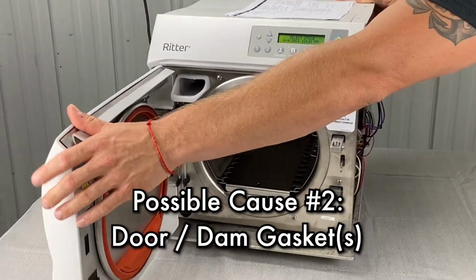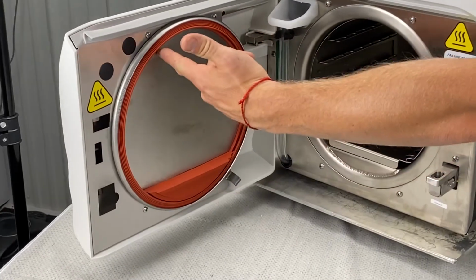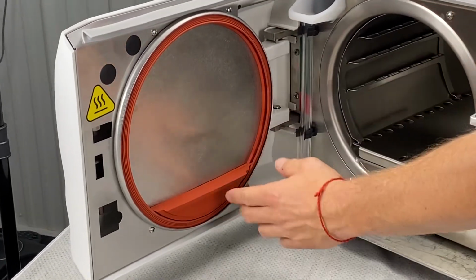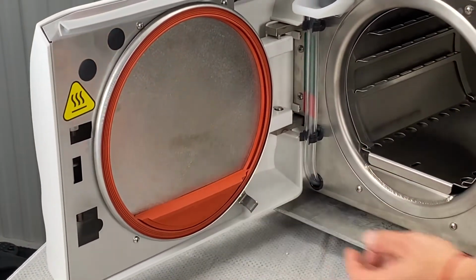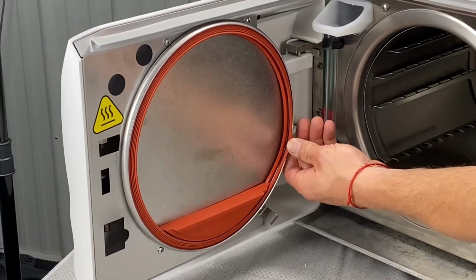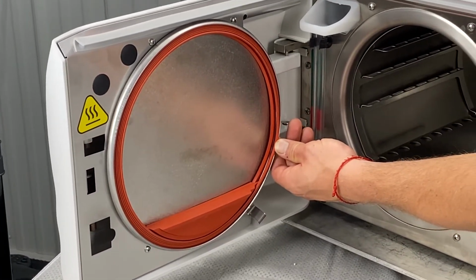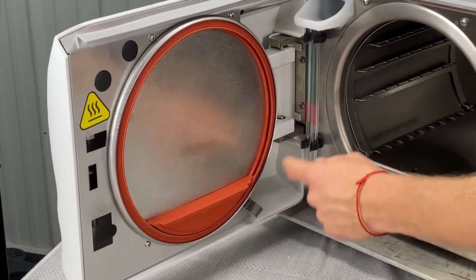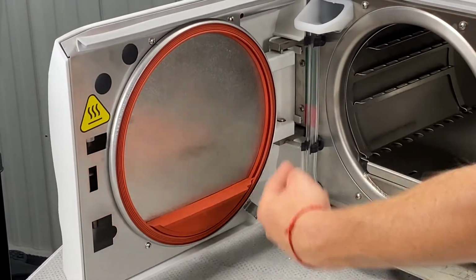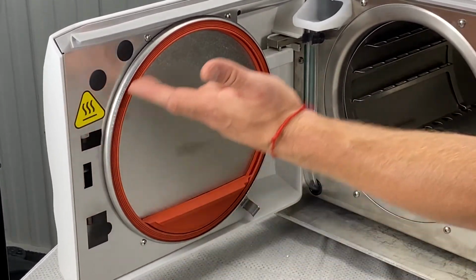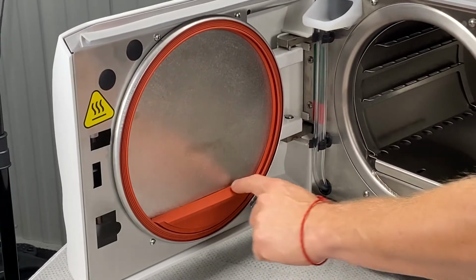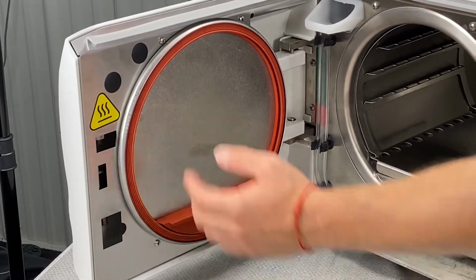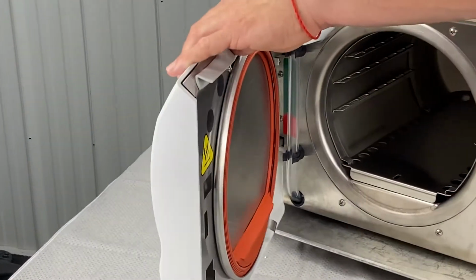Door dam gaskets, we're going to inspect those. They should be replaced quarterly, if not sooner, depending on cycle count and usage. But there should be a door ring in there. If you don't have one, you should get one. It makes the gasket last longer. But anyways, we're going to make sure that this is positioned properly, not sticking out anywhere. The dam gasket sits inside of the door gasket itself. We're going to look at that.